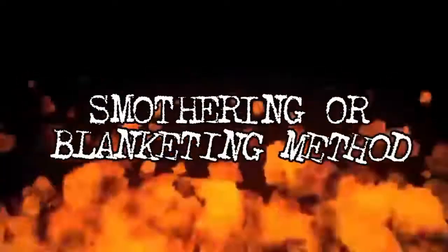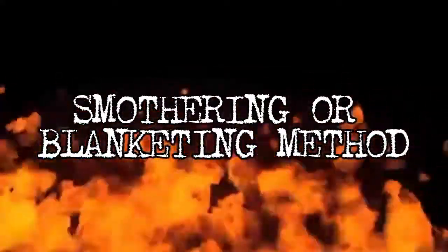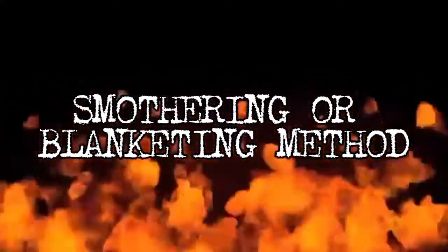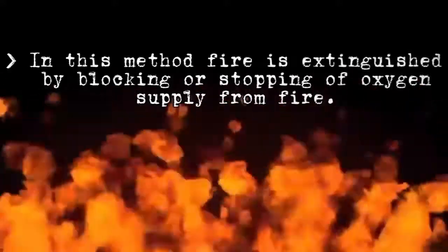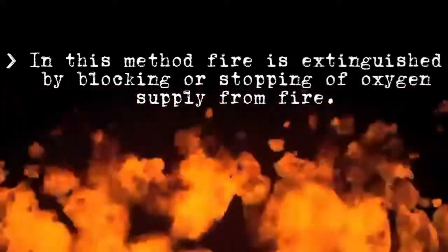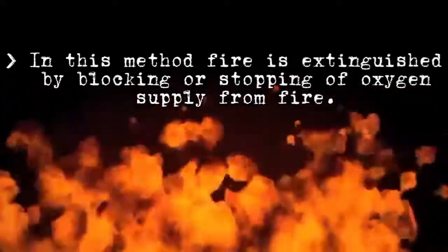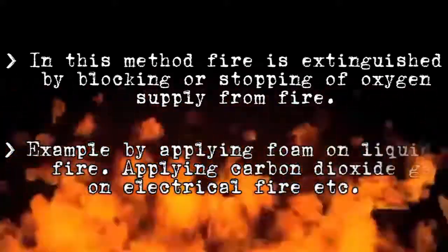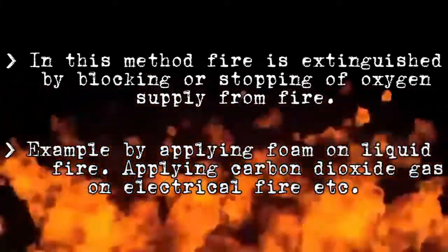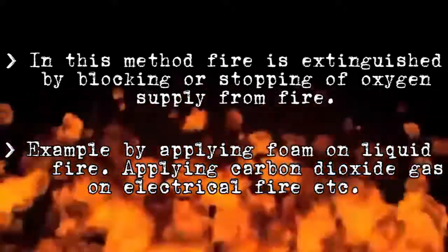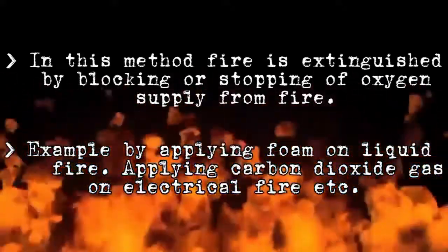And the second method is the smothering or blanketing method. So in this method, fire is extinguished by blocking or stopping the oxygen supply from the fire. Example, by applying foam on liquid fire or applying carbon dioxide gas on electrical fire, and etc.